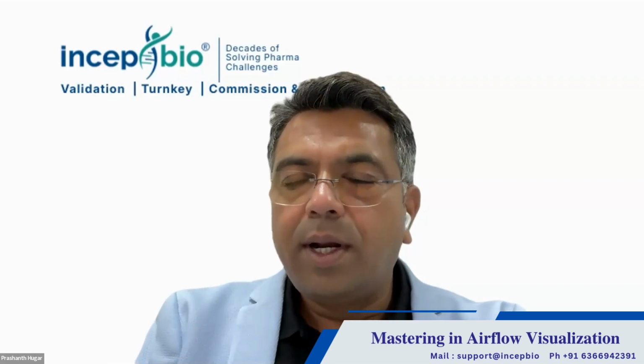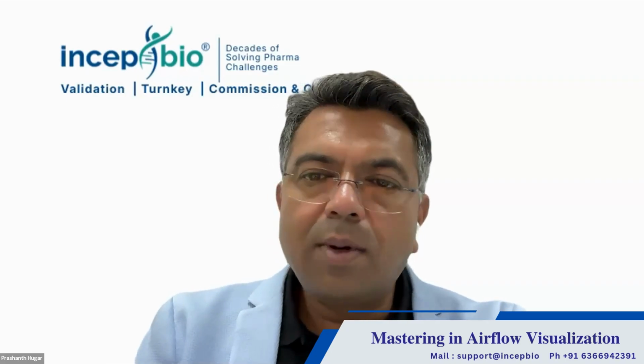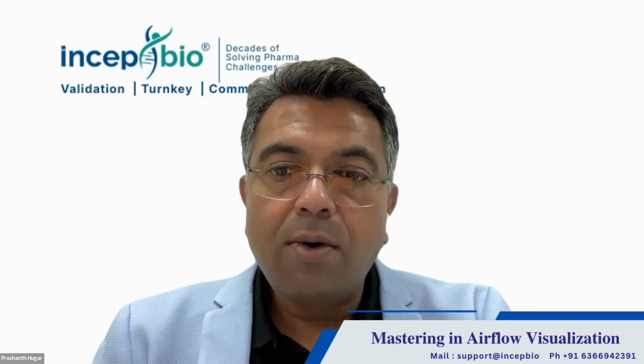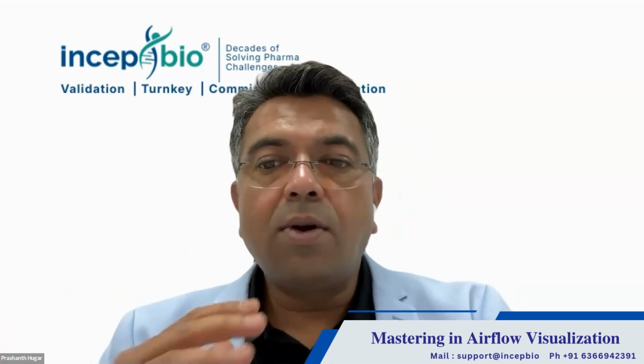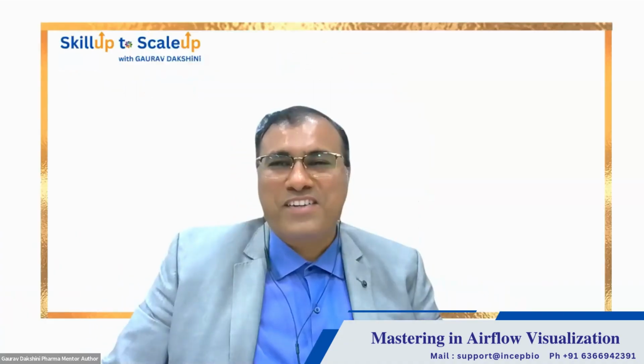There's a question from Anand: What do current regulations such as EU GMP Annex 1 and US FDA state regarding door opening simulation during airflow visualization? Should the airflow be demonstrated with the door fully open, or partially open like 75%, 50%, 25%? Since different clients follow different practices, as a validation service provider, how can we standardize our approach when client expectations differ from one side to another? Okay, very good question, Anand.